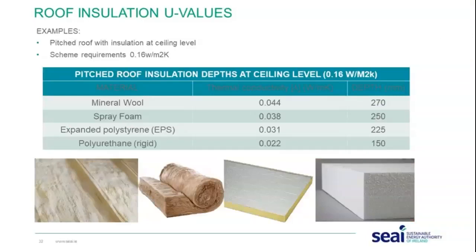For a pitched roof at ceiling level, the scheme requirement is 0.16. There are four different materials with different thermal conductivities, each requiring different depths to achieve that U-value. For example, mineral wool with a thermal conductivity of 0.044 would need 270 millimetres. As you move down to materials with lower thermal conductivities, the depth required decreases, giving a general outline of the different depths needed to meet the 0.16 U-value.